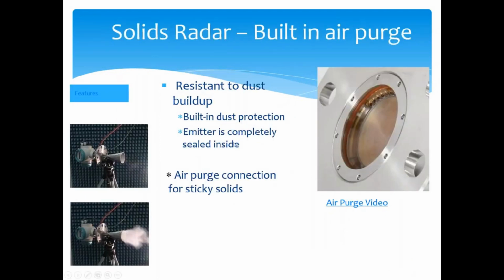One of the other things we can do to prevent dust or buildup inside a radar transmitter is an air purge. Our LR560, one of our solids radars, comes with an air purge built in, and other radar we offer can be provided with an air purge kit. So just something to keep in mind if buildup or dust is a big issue for you inside a horn, and for whatever reason you can't use that Teflon cover.